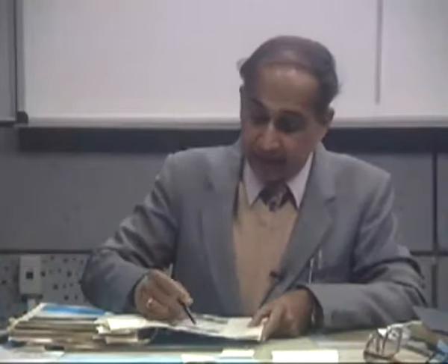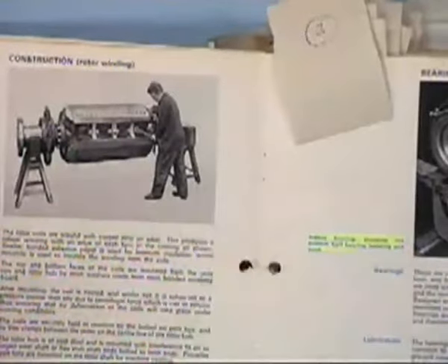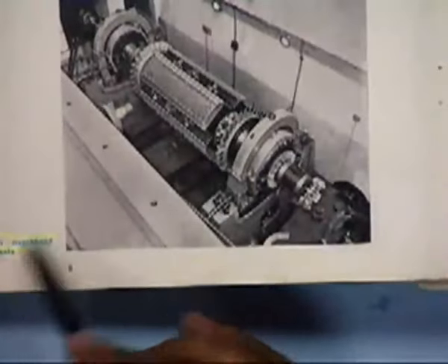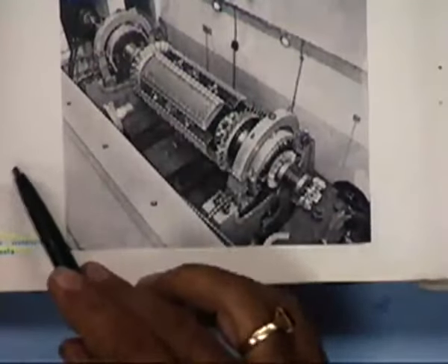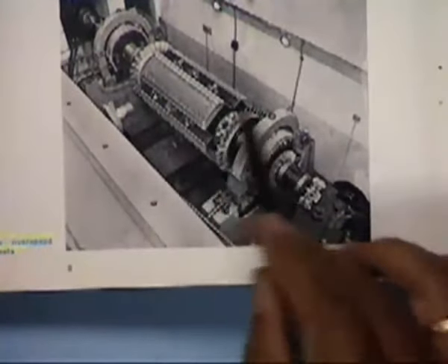Here is again a field winding under construction, the salient pole, and this is a 4-pole rotor in an overspeed chamber. Again it's undergoing test. While earlier we saw a cylindrical rotor, here is a salient pole, it is going for overspeed testing here.